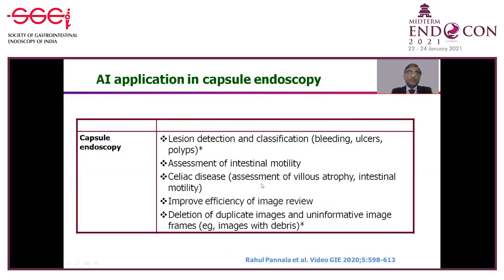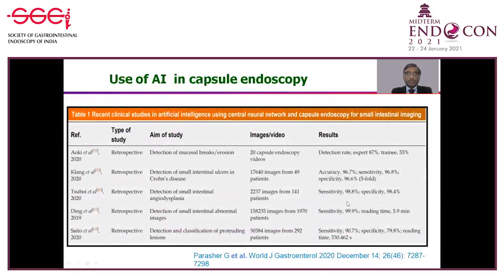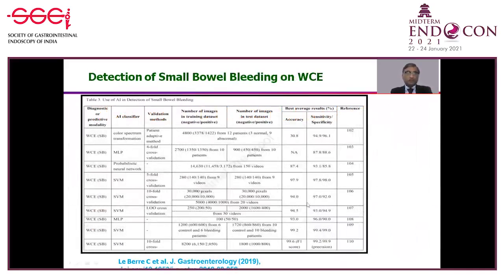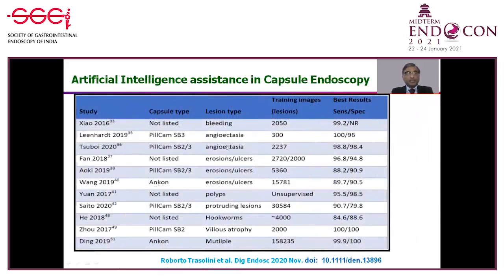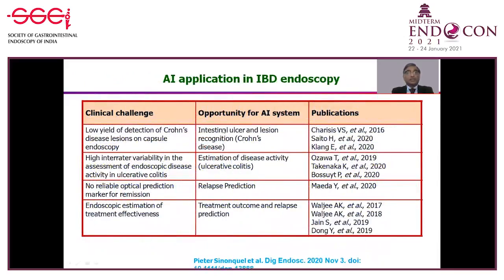AI has also found wide application in capsule endoscopy for detection of lesions, assessment of motility, improving image review, and assisting the endoscopist by deleting duplicate and uninformative images. Systems already available automatically detect lesions and blood with pretty good sensitivity and specificity. Detection of small bowel bleeding, angiodysplasia, villous atrophy for celiac disease, and multiple other lesions have all been studied with very good reliability.